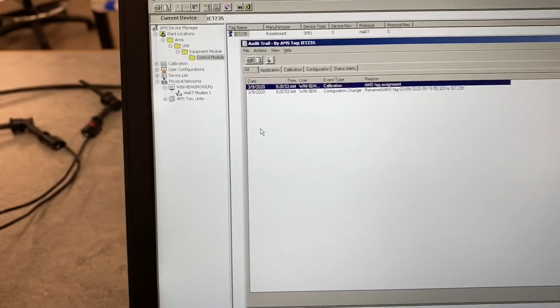Now that we have the device added, we can right click again on the device and go to audit trail. This is what we want to see — the audit trail shows us the history on the device, so we can track changes, whether we replace the device, calibrate it, or perform any maintenance.